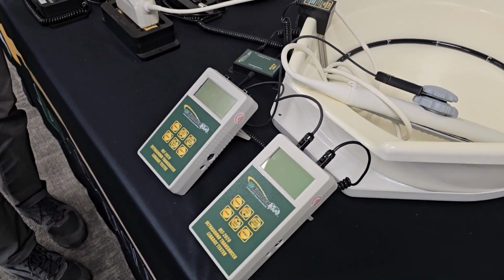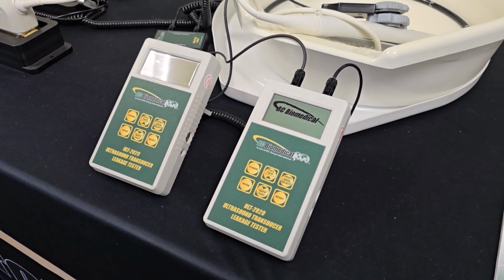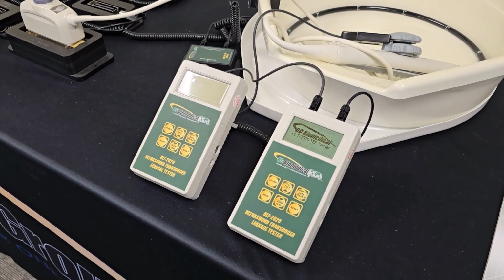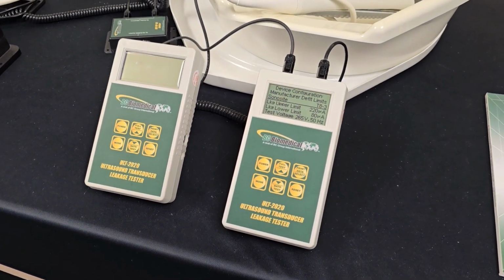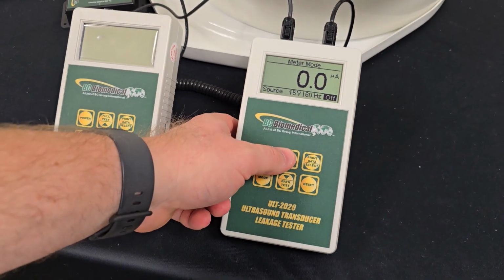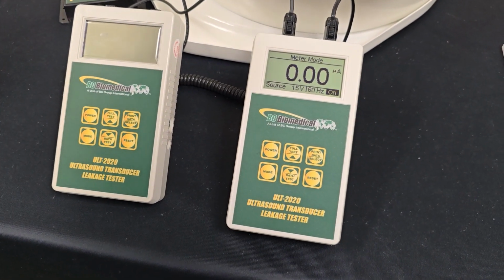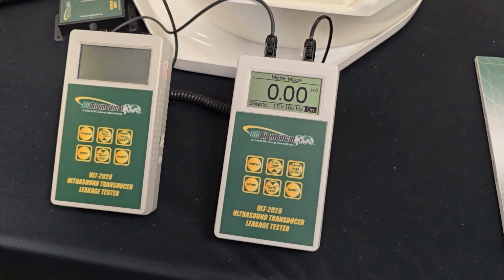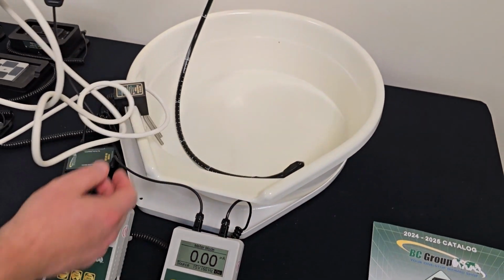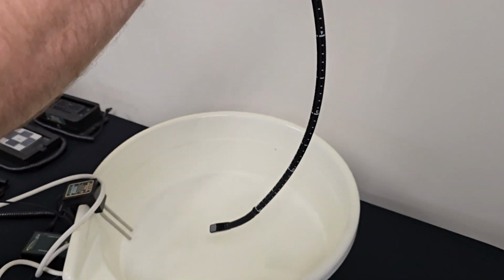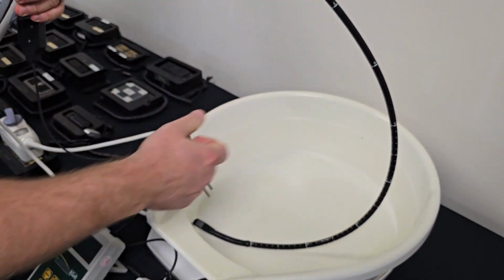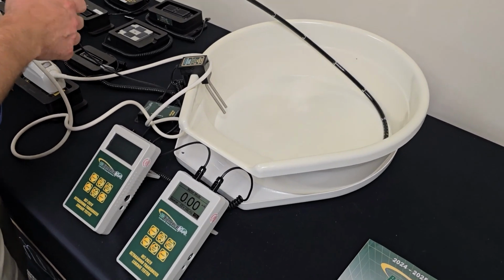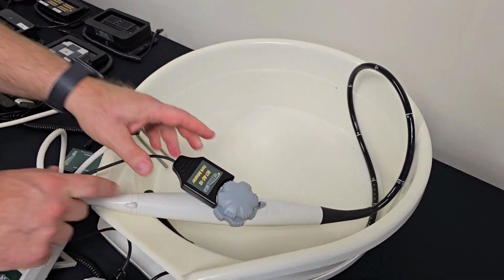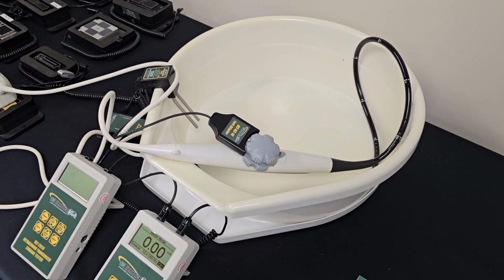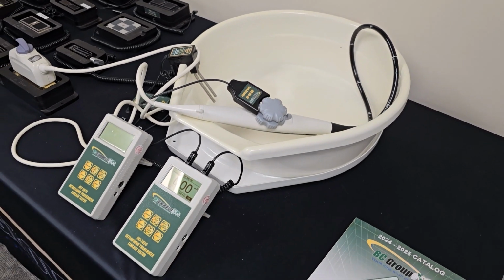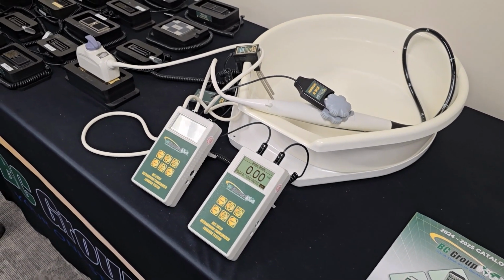Interesting. Okay. Now the benefit of that also that we provide in this product line is that we have a meter mode. So when using the meter mode, we actually run as a multimeter. Okay. So essentially if you failed the test, you can take the transducer and dip it into the water, and at some point you can find when the current peaks. That's cool. So now, rather than just finding bad probes, you can find where it's bad and you can repair it rather than waiting until it's a catastrophic failure and having to replace it. So it saves a lot of money.